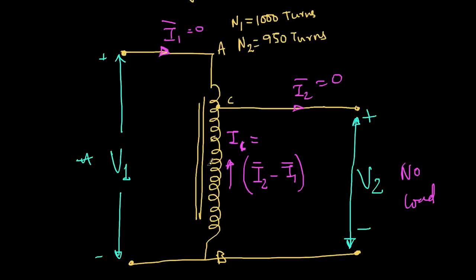And also there is an equivalent resistance working component. So this I1 will be nothing but I naught. And as always, as for the regular transformer, this I naught will be like 2 to 3% of the total current. So we can actually ignore it for the time being because I want to explain the working principle of it now.